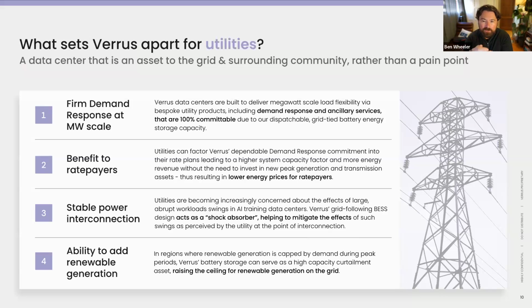The obligation to do that is decoupled from our design because we're satisfying the demand response call from the utility through the battery system as the main interface. As we run the data center off the battery, the state of charge decreases, and we send a signal to our customers that we're in a demand response event. If they wish to curtail to help the effort, they can, which preserves the battery's state of charge longer. If they don't want to, it's within the SLA agreement for backup capacity, and they'll just run with a little lower backup capacity.